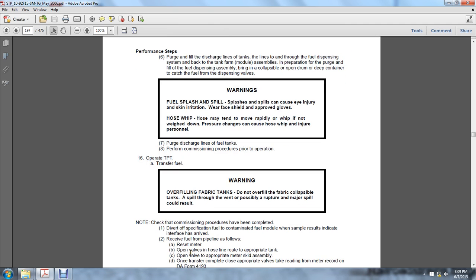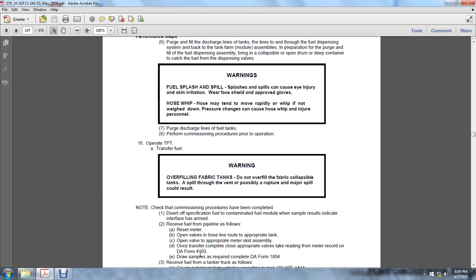Reset the meter. Open the valves in the hose line. Route to the appropriate tank. Open the valve to the appropriate meter skid assembly. Once the transfer is complete, close the appropriate valves to take in the reading of the meter, recorded on DA Form 4193. Draw samples as required to complete the DA Form 1804.